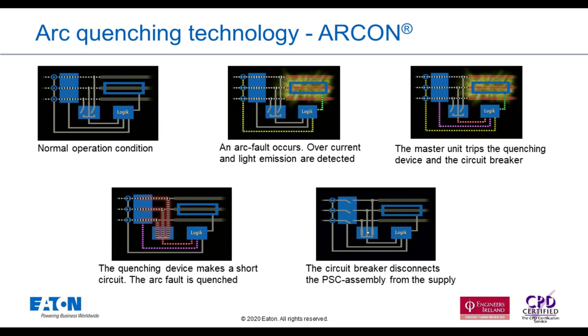So let's just explain how the Arc-on technology works. In the first picture, you can see there are several parts to an Arc-on system. You've got the detection, which is through the fibre optical cable running alongside the bus bars, in conjunction with some CTs which are monitoring the current, and you've got a piece of software that evaluates the signal. Then you've got the arc quenching device itself, and then the disconnection of the circuit. Picture one shows the system in normal operation: current sensors, the main incomer, the quenching device, the bus bars, the light sensors, and the master sensing unit all working passively together. So in normal operation, it works as normal.